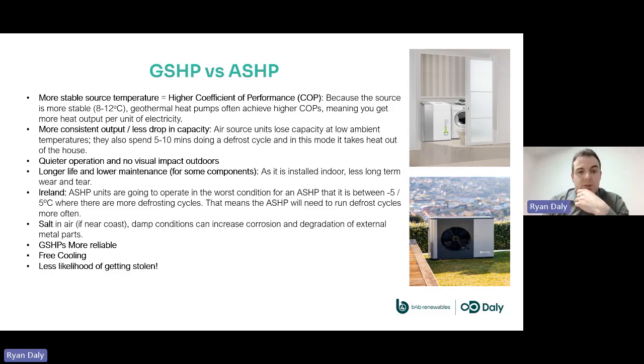More consistent output. So obviously in the winter months, the air source heat pump has to do a defrost cycle. And when it's doing that, that could be 5 to 10 minutes of taking energy back from the house and getting the heat pump defrosted and getting that temperature built back up again. So obviously you don't have that loss with the ground source heat pump. Quieter operation and no visual impact outdoors.